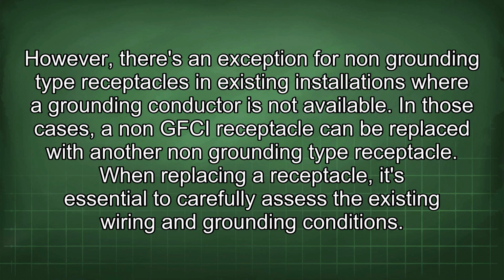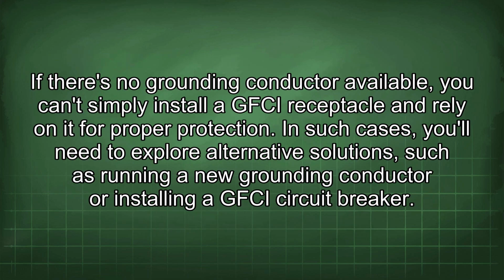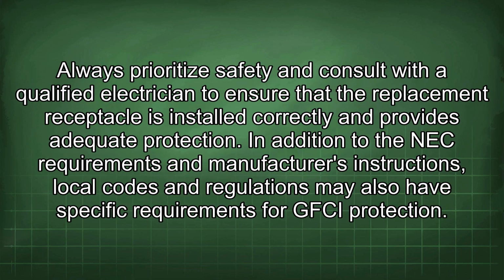When replacing a receptacle, it's essential to carefully assess the existing wiring and grounding conditions. If there's no grounding conductor available, you can't simply install a GFCI receptacle and rely on it for proper protection. In such cases, you'll need to explore alternative solutions, such as running a new grounding conductor or installing a GFCI circuit breaker. Always prioritize safety and consult with a qualified electrician to ensure that the replacement receptacle is installed correctly and provides adequate protection.